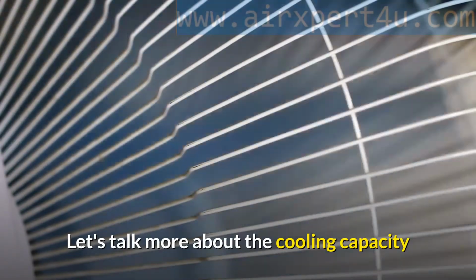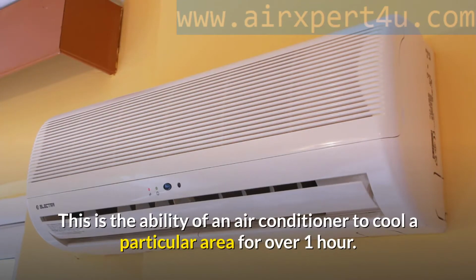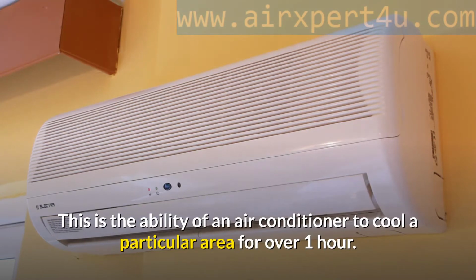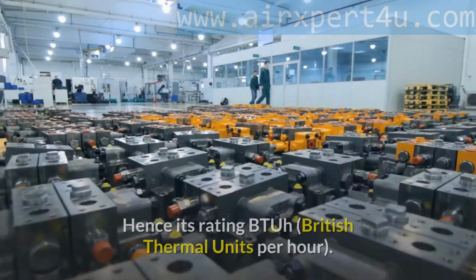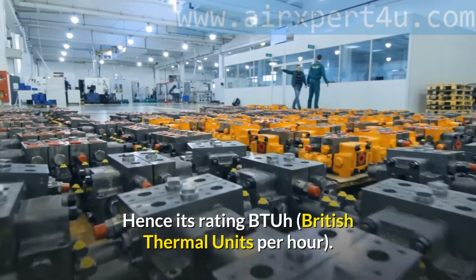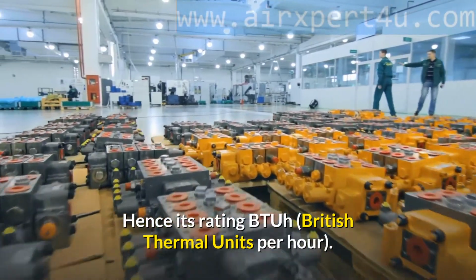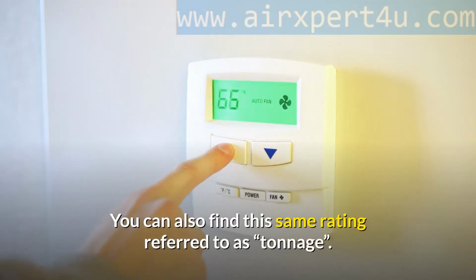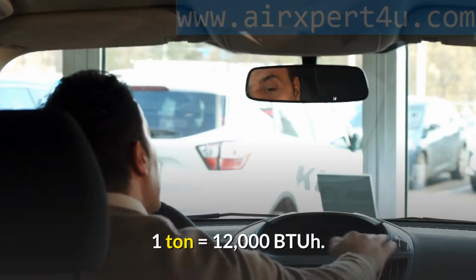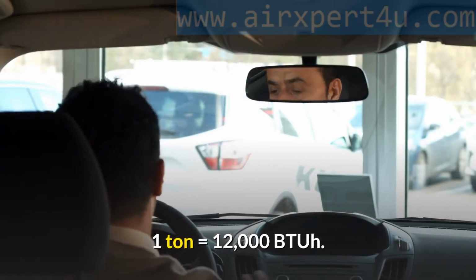Let's talk more about the cooling capacity. This is the ability of an air conditioner to cool a particular area over 1 hour. Hence its rating BTUH, British Thermal Units per Hour. You can also find this same rating referred to as tonnage. 1 ton equals 12,000 BTUH.